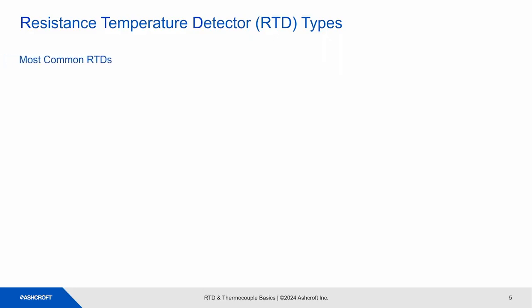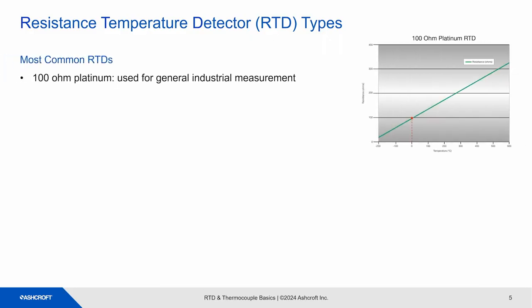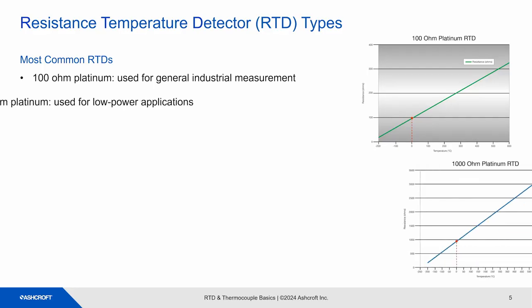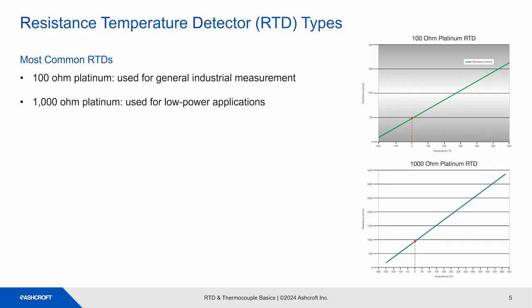The most common RTDs are the 100 ohm platinum, which is used for most general industrial temperature applications. The RTD resistance is 100 ohms at 0 degrees C.